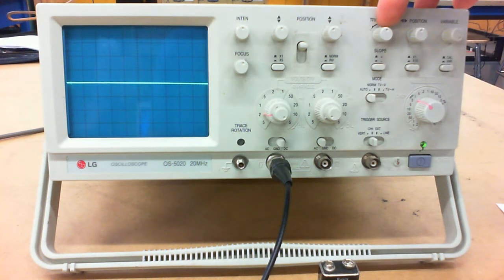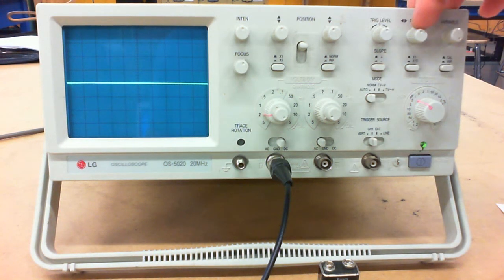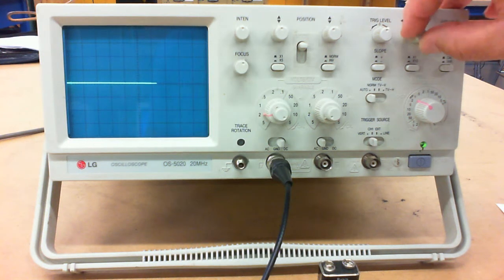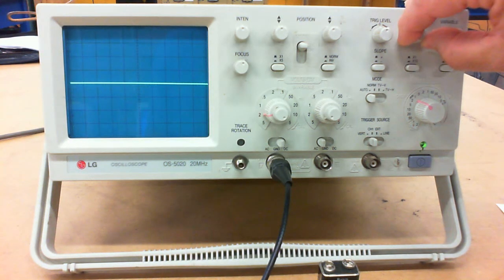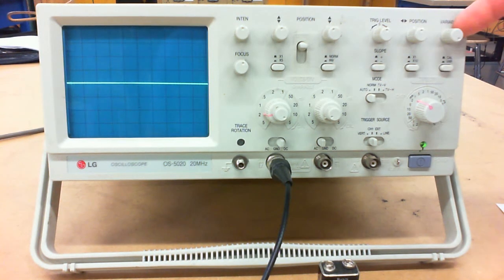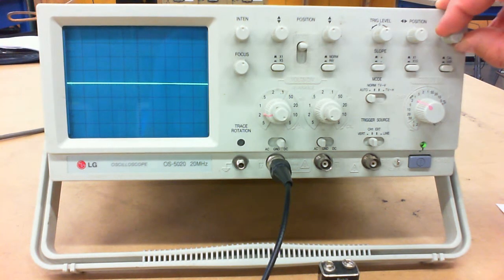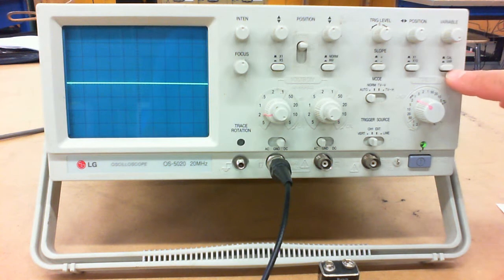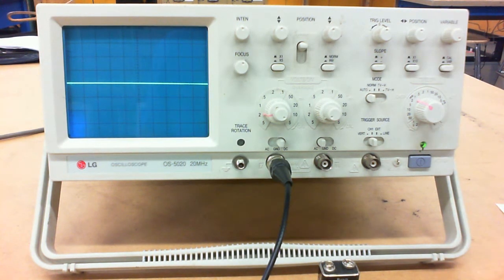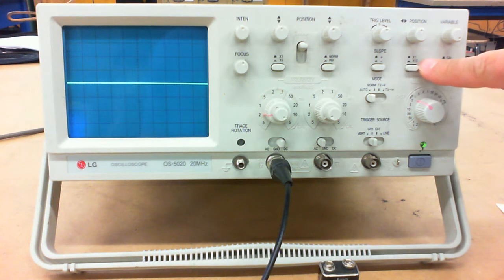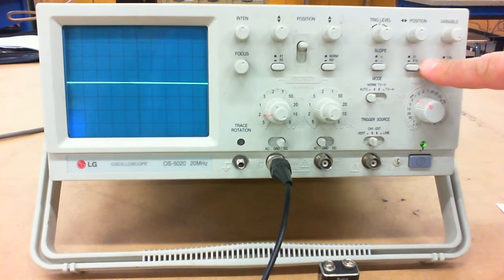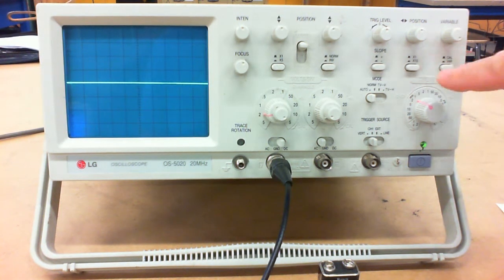I have a trigger level up here. I want it centered. I have a position sideways, so I'm going to make sure that it's in the center so the line shows up all the way. I have a variable that I'm not going to touch, but it is going to be all the way to the clockwise position. I have a variable calibrate. I'm going to make sure that it is out, that it's on calibrate. I have a time magnification. So I want it depressed, so it's not at 10, it's at 1.